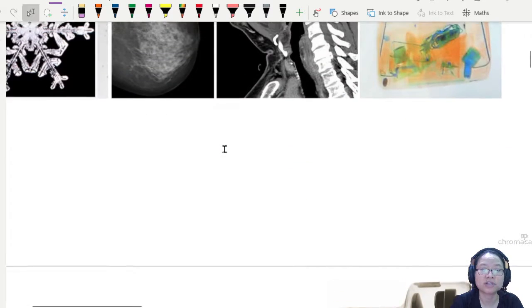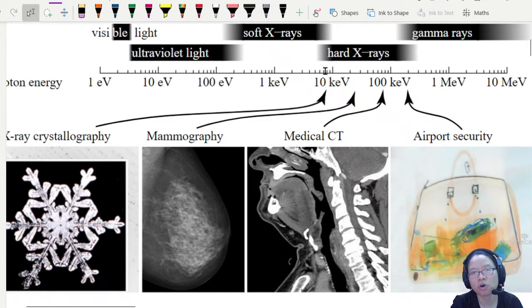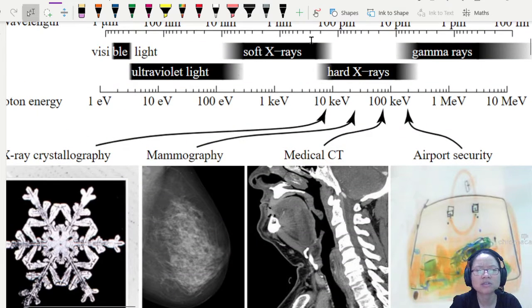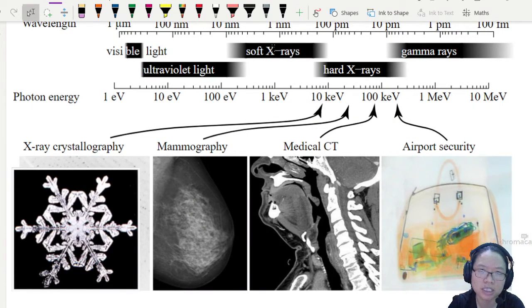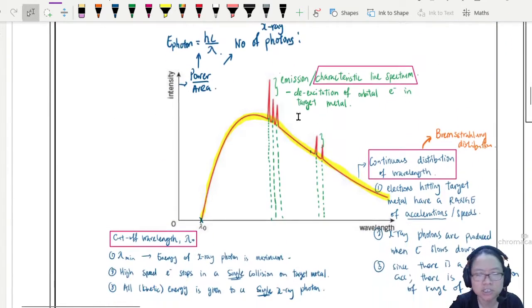If you remember the spectrum that I showed you in the first video previously, there are hard X-rays and there are soft X-rays. For imaging, we all use hard X-ray. We don't even want the soft X-ray. We would like to be able to filter out or not have this around at all. Because although the X-ray is soft, do not be deceived. It is still ionizing, still dangerous.